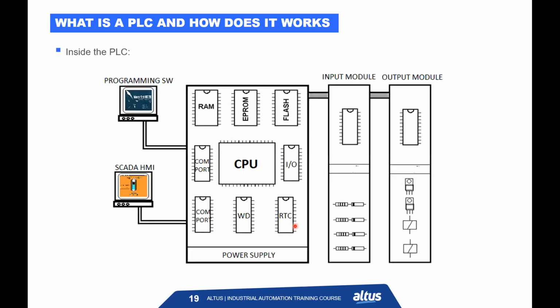Here is basically a picture showing this. We have, of course, COM ports or Ethernet ports that connect to the programming tool, which will receive the interlocks and the application code. And of course, the serial port or Ethernet port can connect to the HMI. We have the memories here, the EEPROM, flash, the I/O storage, real-time clock, watchdog, and of course, everything connected to the CPU, which receives from the input modules, digital or analog inputs, processes the logic, and writes the memory to the output modules.